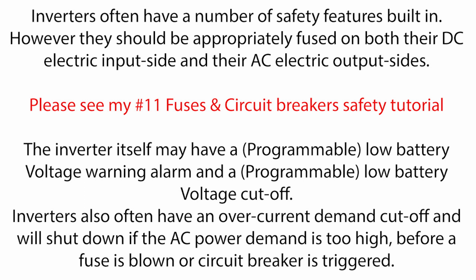catching fire. On the flip side, inverters often also have a low battery voltage disconnect built in. That means if the inverter senses that the DC battery or batteries that are supplying the inverter with power are getting low in power, then the inverter will automatically shut down before the battery is completely drained. This is often something you can program on your inverter. As I will point out, some batteries when run down beyond a certain percentage are often irreparably damaged. This low voltage disconnect feature in many inverters is, as I said, usually programmable for the varying different battery types, for example lead acid or lithium phosphate or LiFePO4. Please see my tutorials regarding these different battery types.